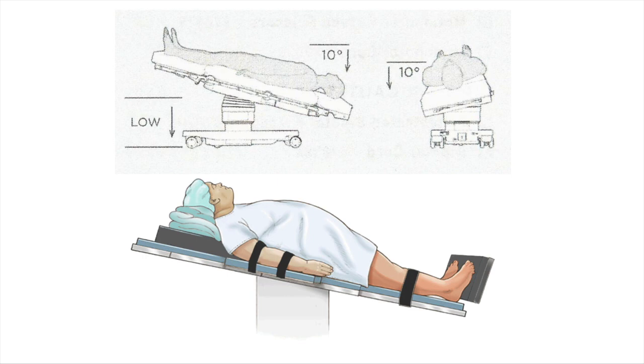This graphic is critically important for SI system users. I remember cases where I literally could not dock the robot because of a patient's extremely obese abdomen. What I learned quickly was that if you need to drop the bed and it won't go any lower, the trick is to slide the bed in the direction it is pointing. If the patient is in reverse Trendelenburg with feet pointing toward the ground, slide them toward the floor. If they're in Trendelenburg with head toward the floor, slide them toward the head — this drops the vertical height, lowers the center of gravity, and allows you to dock the robot. This is far more critical on the SI robot than the XI, but it's still a good point.